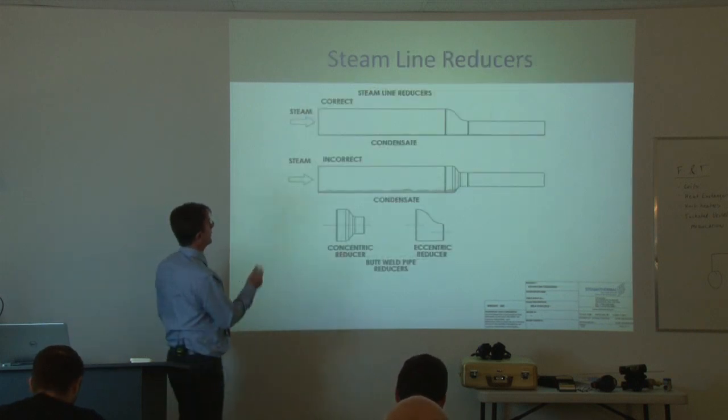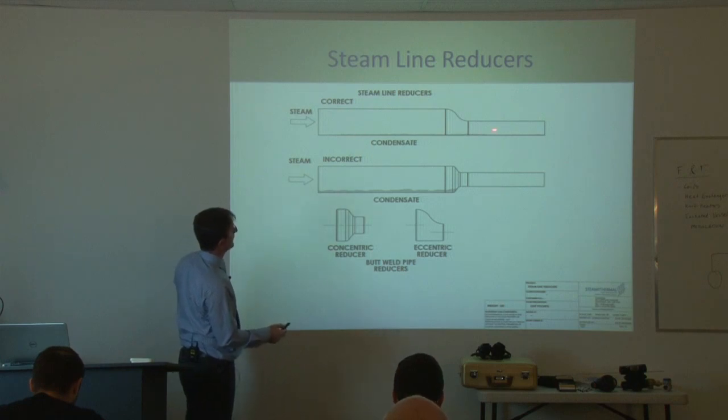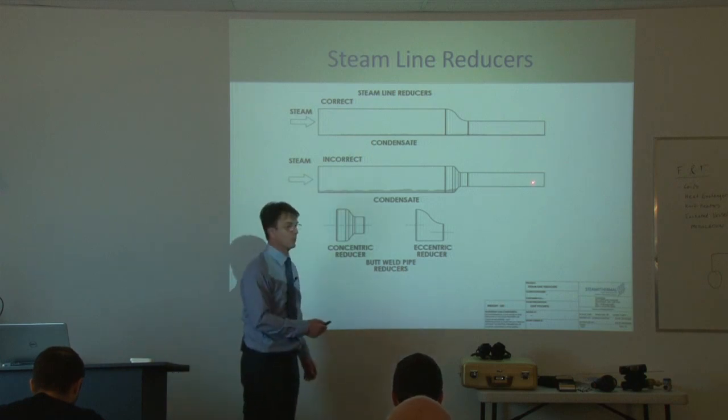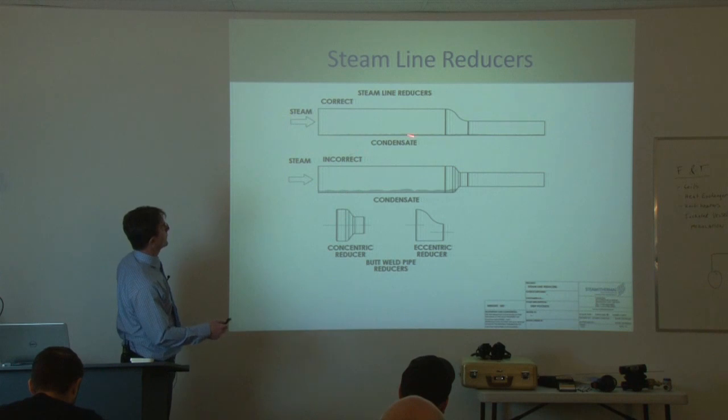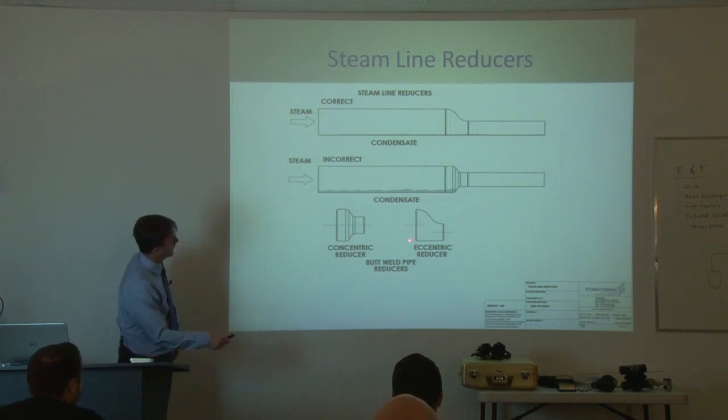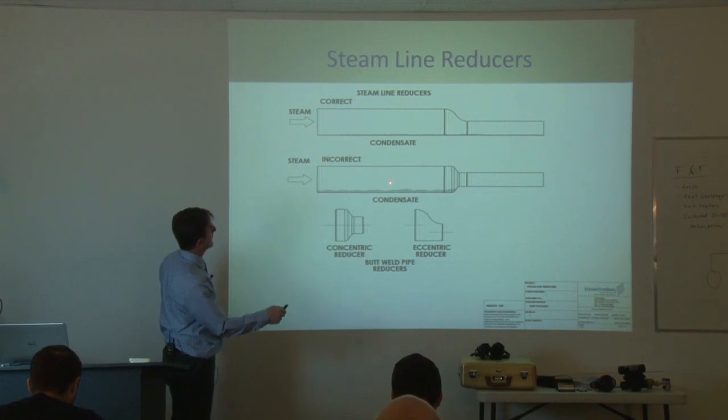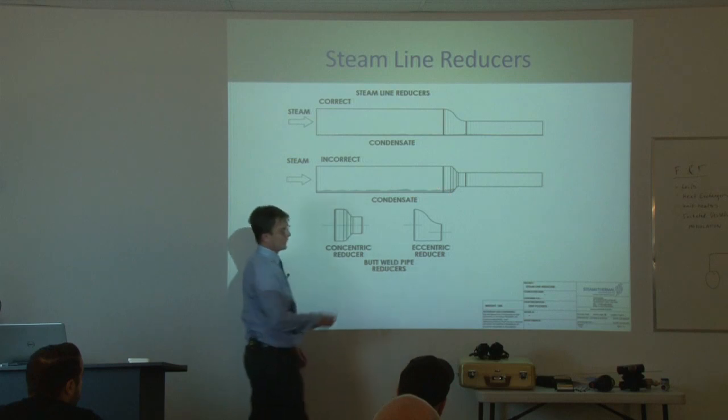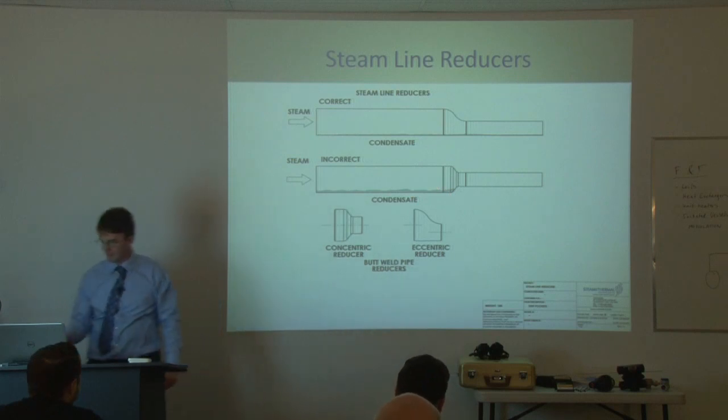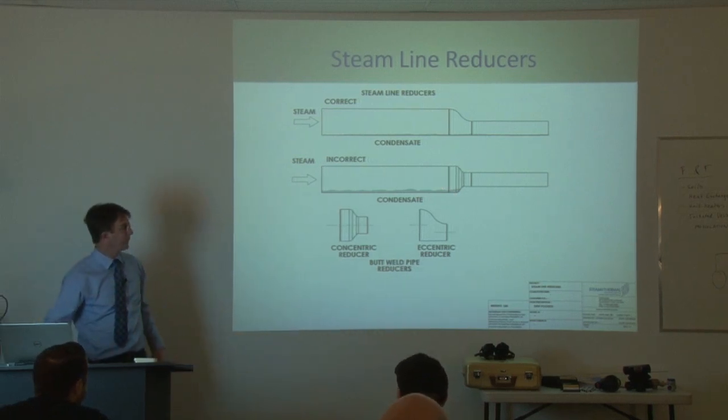And when we're reducing the pipe size, normally when we're going into a control valve or a pressure reducing valve, we'll have to reduce the pipe size. We prefer to see an eccentric reducer instead of a concentric. So the concentric looks like that where it's curved on both sides. Eccentric is flat on the bottom, curved on top. So that way, condensate doesn't have a chance to pool. We're just looking for ways to not having condensate pooling. So this is another one of those little tricks, best piping practices.